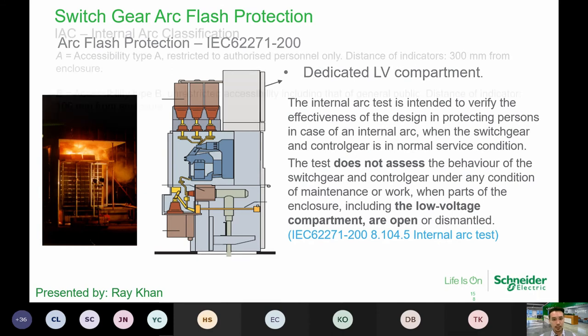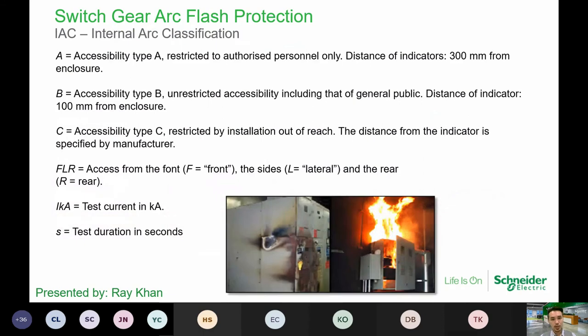Okay, so over in here, it talks about the IEC requirement for 62271. It takes into account a lot of factors, like how it is being manufactured, and also, when there's arcing itself, the FLR, the front, the side, the rear: for the person standing around it, are they protected? So then also the design is that when there's an explosion, would the door be secured so that it doesn't burst open?